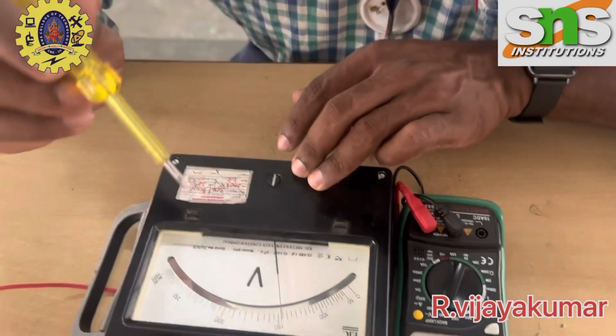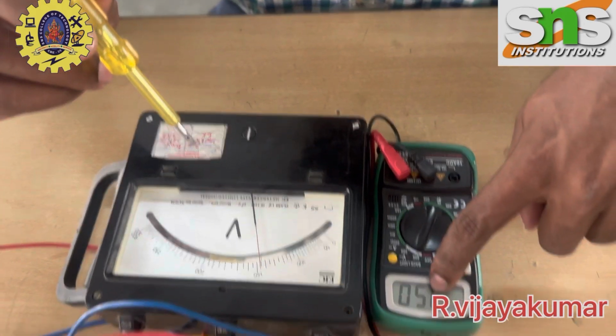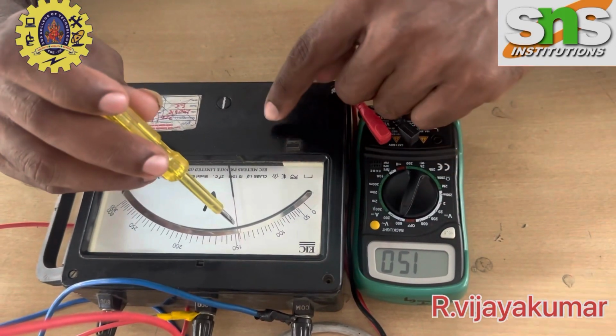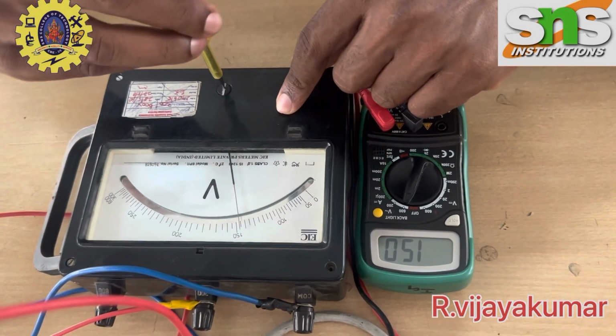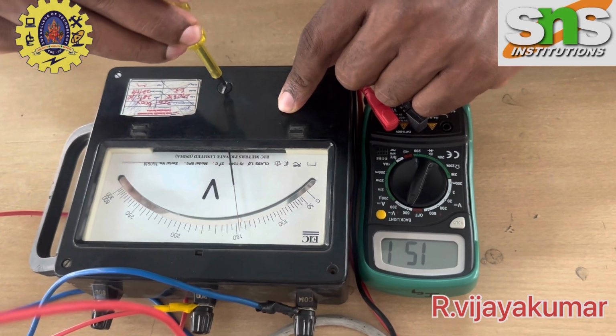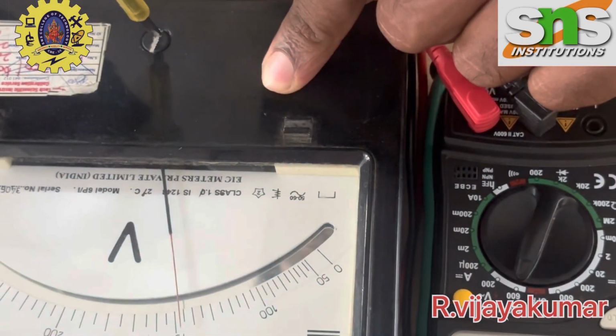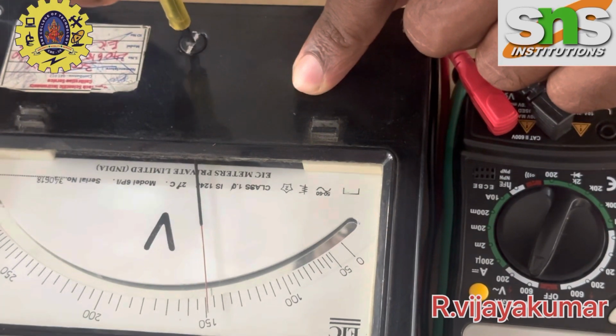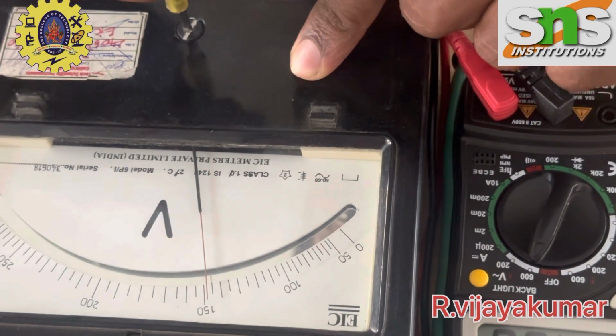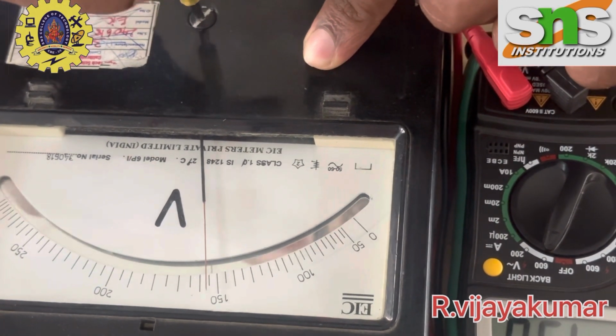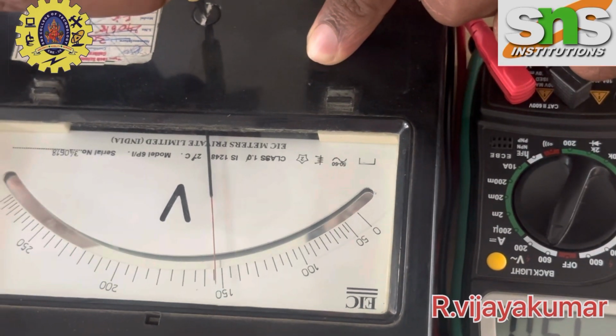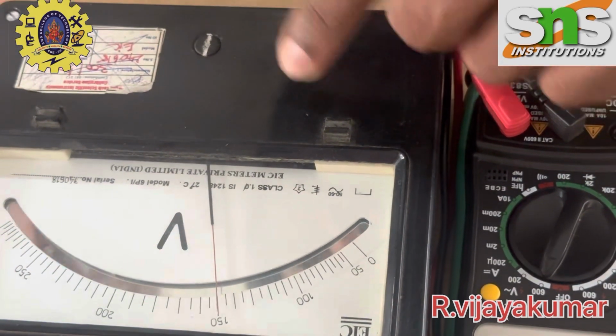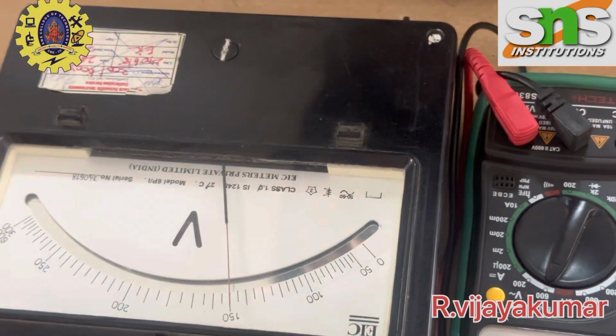Now I am going to calibrate this meter. The digital meter shows 150 volts, but this meter shows 140 volts. So now I am increasing the screw spring pressure. Now the meter reading also shows 150 volts.